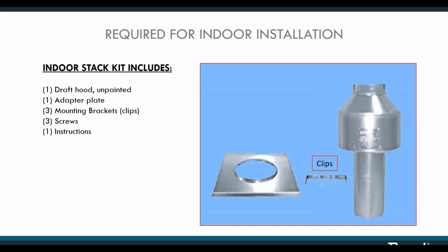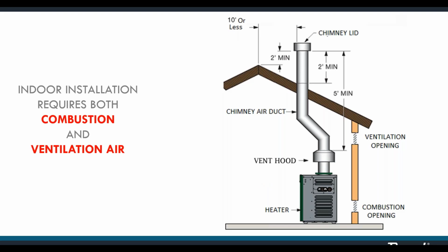To relieve the negative pressure, an indoor stack kit must be included with any indoor installation that comprises a draft hood or a vent hood and the ancillary products necessary to install that hood. So now we have a vent hood. This allows relief air to be pulled in without disrupting the flame below. So now we have the same thing going on. We got air coming up, okay? Hot fumes are going up through that pipe, creating a draft. Only now that negative pressure, that draft begins to pull air in from underneath the hood and not underneath the heater, okay? So we fixed that problem, but we created a brand new one.